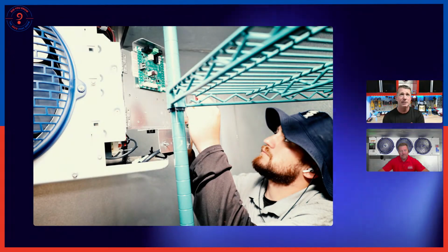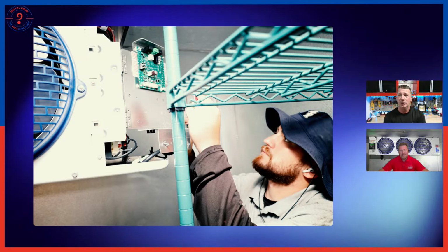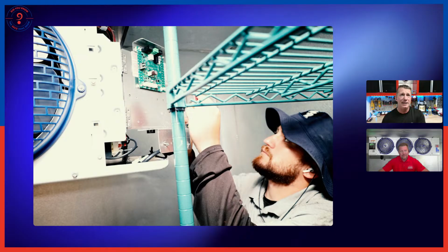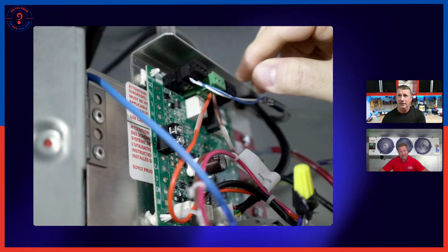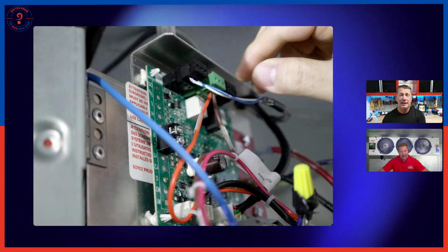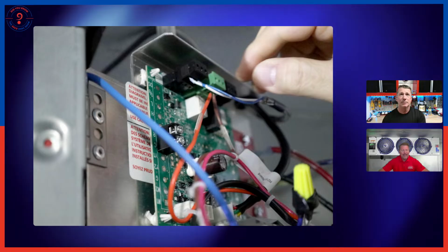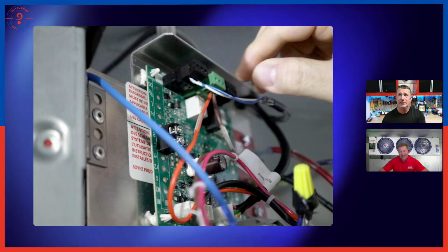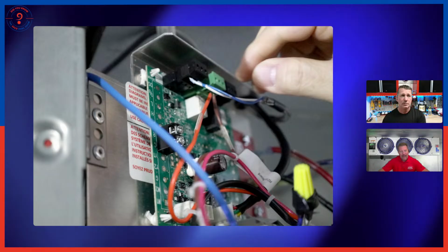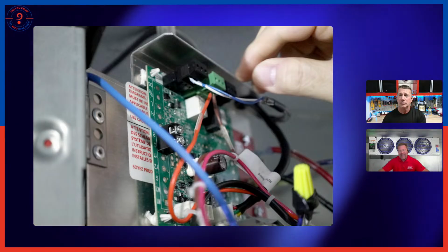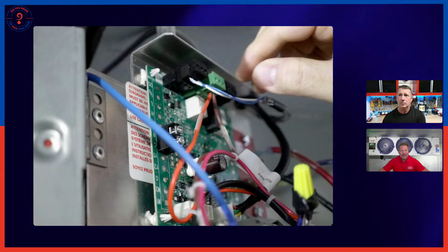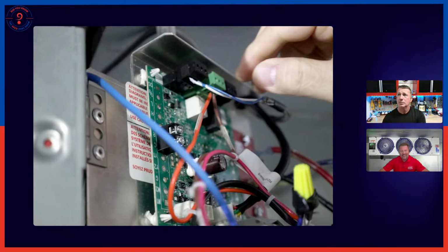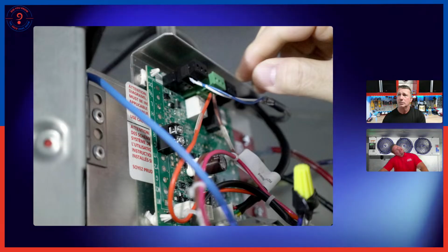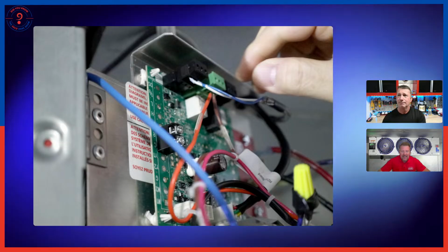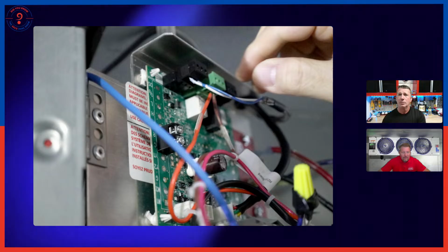And I love this swing out control that you've put on. I've seen them on a variety of different coils, but now with that A2L, that gives us the ability of having the A2L control very accessible from the side by swinging out the control. And engineering listened, guys, technicians in the field, engineering listened. This can be swung away and accessed even when the product is in the box. You can swing that and see it from the front. You're not over there with your neck in this position trying to get in there to see a blinking light or anything like that. This will fully swing away.